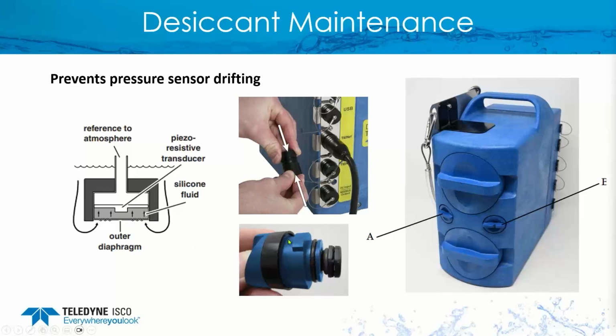Now, a couple other things as far as with this desiccant. With our equipment, we have a Gore filter, as you can see here in that bottom middle picture. And what that Gore filter does is added protection for the desiccant. So if the unit were to go underwater, the Gore filter or a hydrophobic filter will actually prevent water from getting inside of the desiccant tubes. And so in the event that the meter does go underwater, it's submerged, due to high water levels, the one thing you'll want to do is pull out your desiccant tubes, replace the desiccant beads, and I recommend replacing that Gore filter because by design, it's supposed to plug to prevent water from getting inside the system.